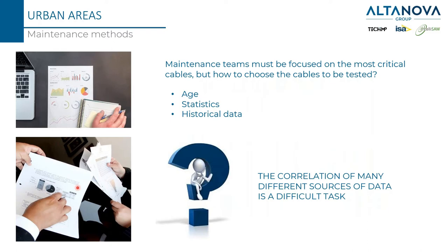Because whenever you apply this kind of high voltage, if there is a defect, in order to amplify the signal from that defect we are also worsening the condition of that defect — so the remaining life of the cable is reduced. Another issue is that the information from these standard routine tests must be analyzed separately. In the end, people decide which cables to test according to the age of the cable and historical data, and correlating many different sources of data is a really difficult task.